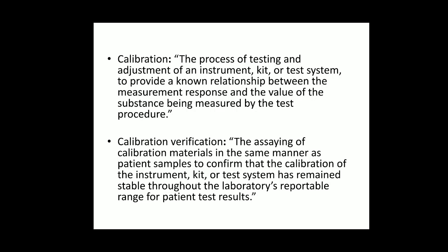Then calibration. So what do you mean by calibration? I told you QC we are doing to check if our instrument is giving out proper values or not. Suppose it is not giving, then we have to calibrate it, so the system has to undergo calibration. In calibration, the process of testing and adjustment of the instrument is done. Once it is calibrated and adjusted, then again we put the QC and see whether it is giving a proper report or not.